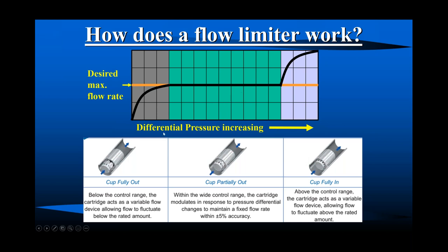If it gets to the point where the differential pressure across this device increases, it'll bottom out. Those circular openings are still exposed to the flow. So again, we're a fixed orifice, but flow will go through it. So this green area, if you will, is where the flow limiter does its work.